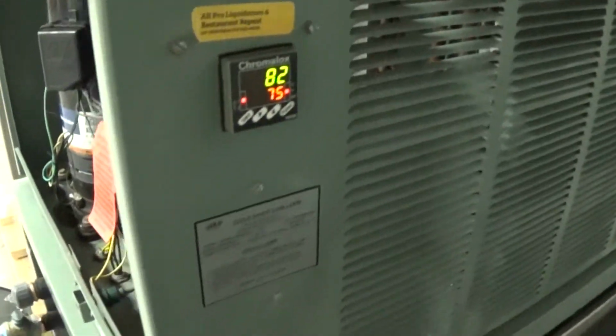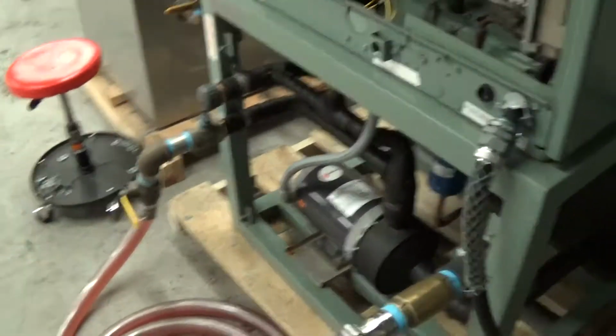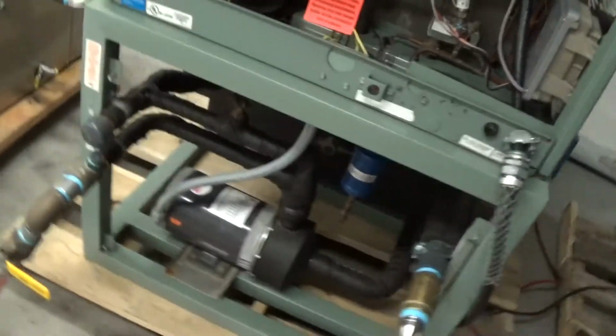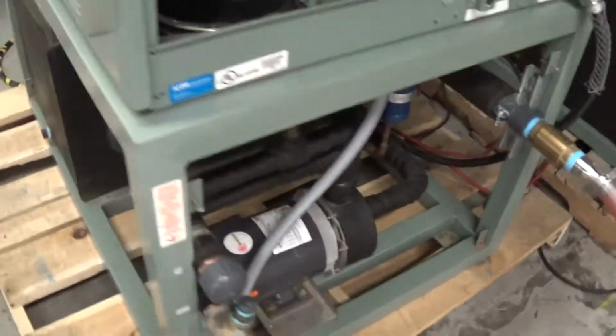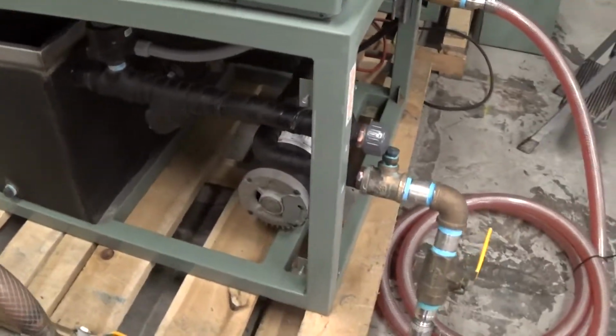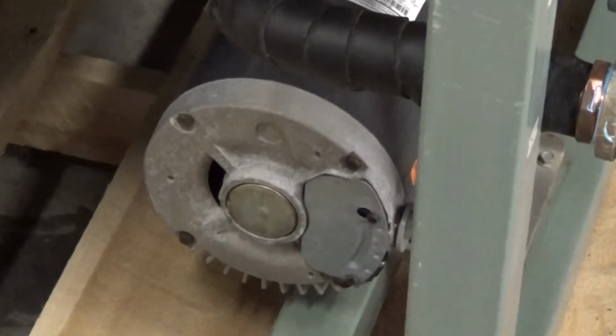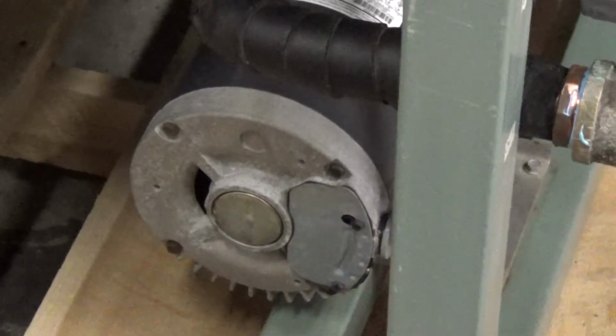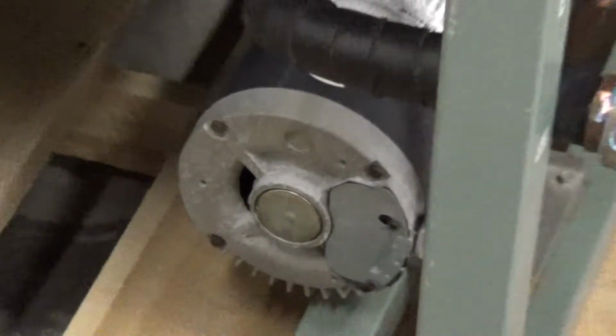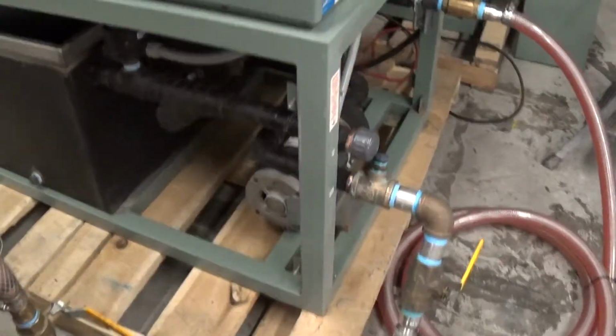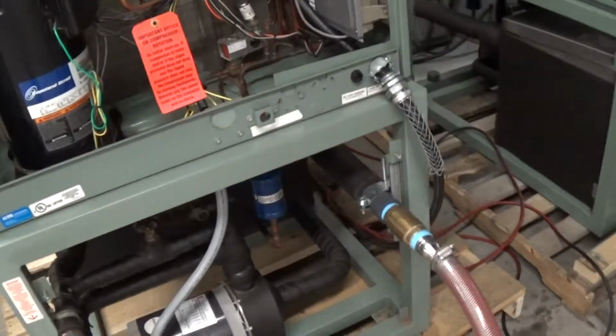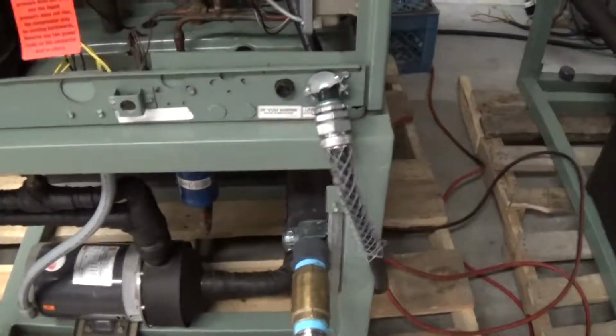what you want to do is with the helper, you want to get behind, you want to confirm the pump rotation. The compressor rotation is very important and the pump rotation too, they're synchronized. Looking in the back of the chiller, you want to go clockwise while looking from the back. Now if you get a flashlight and look through there while somebody just bumps that switch, going from off to pump, you'll be able to see if you got the right rotation. If you don't have the right rotation, then you should change.